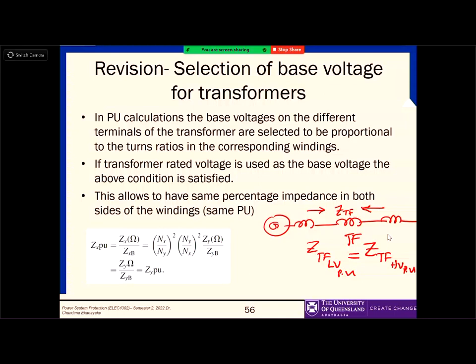So you're saying if you use a tap changer and go from 11 to 129, you have to use 129? Not the primary side, that stays at 11. The secondary side can change slightly, from 129 to let's say 133. So if you are using a 129.5 tap change, then you have to use that corresponding voltage on the secondary side as the base. Otherwise, the impedance will not be equal from both sides when you look at it. That's because it comes from the turns ratio, and we can prove it. I have the proof on the next page. If you maintain the turns ratio equal to the voltage ratios you use, then the impedance looking from the primary side and secondary side will be equal. We need to make it equal because everything is put on one line. That's the reason.